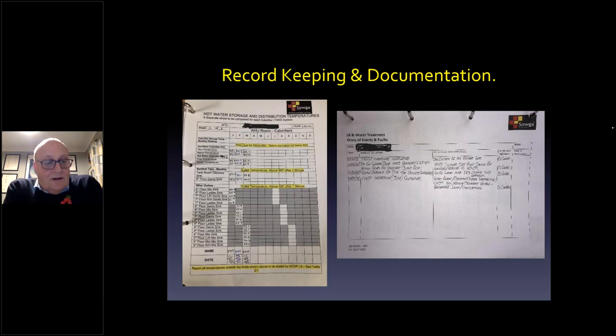If you are in London or in big built-up areas, in the summer months, which we identified earlier as between June and October, where we have higher temperatures, the incoming water coming into your mains, into storage tanks, or into your building will be the majority of the time above 20. Not a lot you can do about it, to be honest, unless you put cooling systems in. But you've got to be able to take action, log those down as non-conformities, and put in the remedial actions that you're going to do.